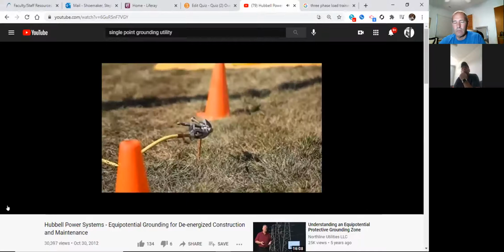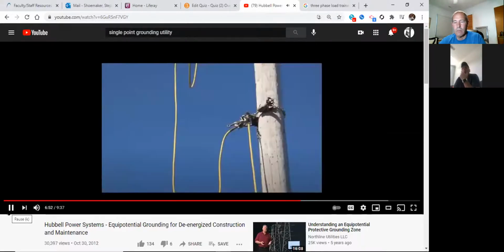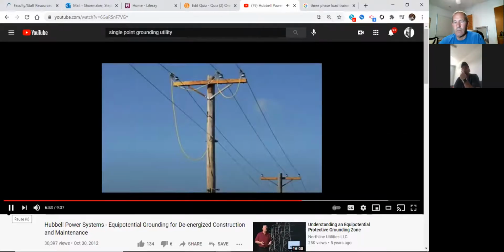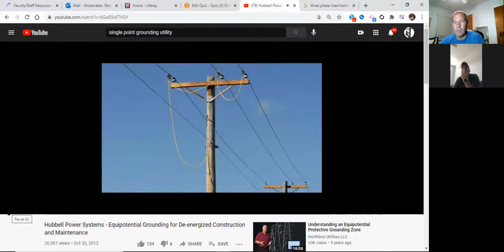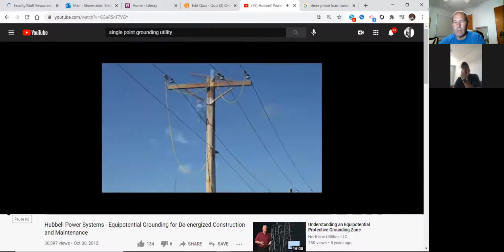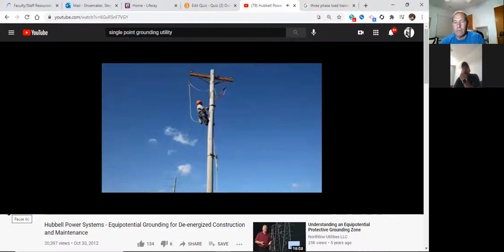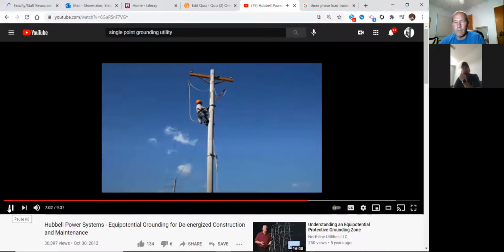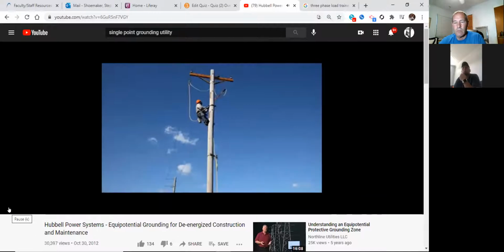The 5 grounding sets, from the ground rod to the cluster bar to the neutral and all 3 phases, now join together in one grounded circuit. With the grounds applied at a pole one span from the worksite, we move to the pole one span away from the worksite in the other direction.